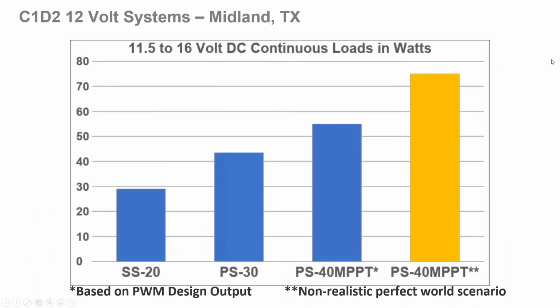Okay, so now we're going to be moving on from a specific real world example, and talking a little bit about this future design architecture around these new Morningstar charge controllers, particularly the ProStar 30 and the ProStar 40 MPPT, since those are the higher current rated charge controllers to have this new Class 1 Division 2 certification. Looking at this chart, on the y-axis we have the average continuous load in watts that is supported by each one of these charge controllers. No surprise that going from a Sunsaver 20, we're approximately doubling our continuous load going to a ProStar 40 amp.